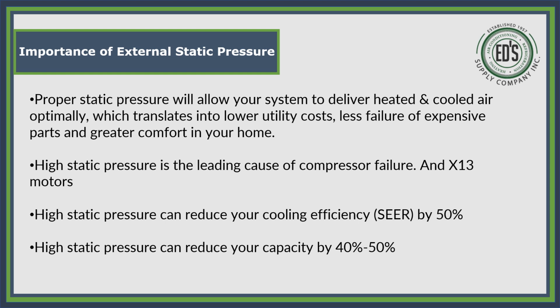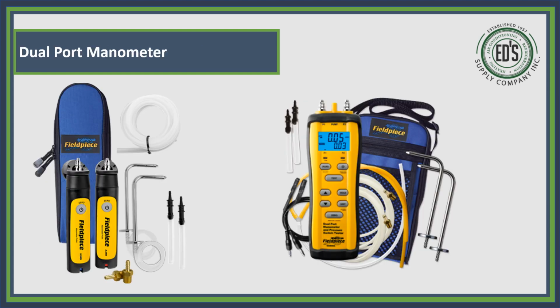High static pressure is the leading cause of compressor failure and X13 motor failure. High static pressure can reduce your cooling efficiency SEER rating by 50%, and high static pressure can reduce your capacity by 40 to 50%. That will probably shock you, and we will recap some of this in a little while, but we're going to show you exactly why this is.